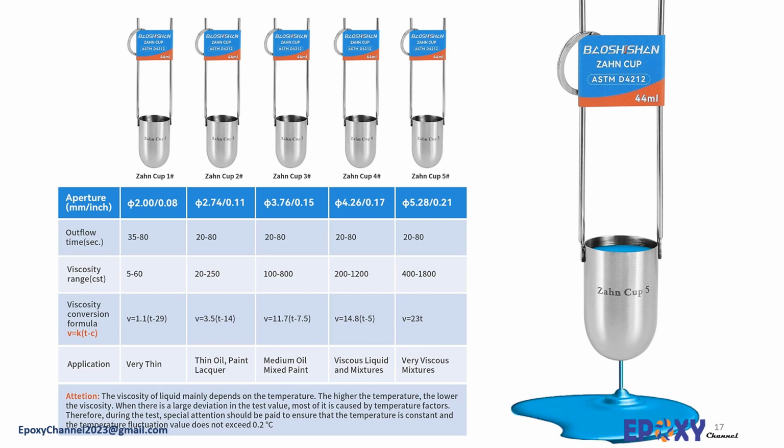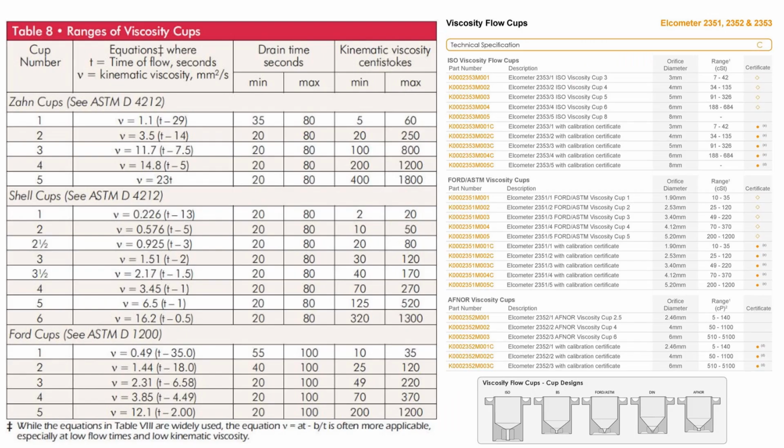Properties of different Zahn cups have been shown here as well. Here an overview of all different cup designs and the formula to convert the time to the viscosity have been presented. It is a valuable source for your future reference.